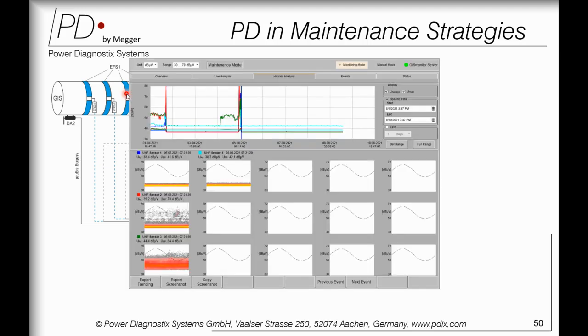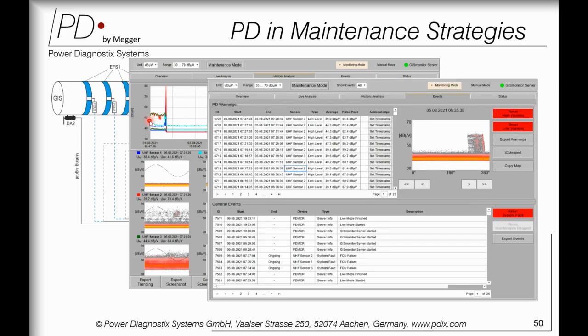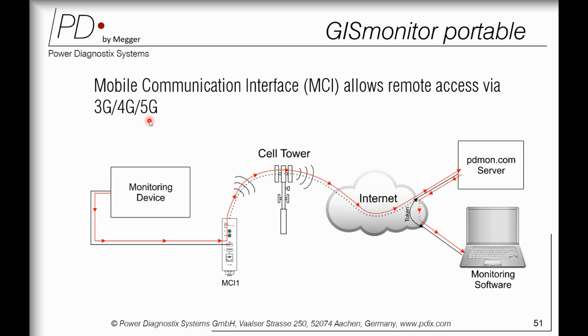The software is capable of temporary monitoring. You can connect up to 8 channels and go up to 40 channels in future, where you capture the PRPD patterns. You have a voltage where you do the trending, along with date and time and dB microvolt values. It also captures all the events, each and everything, because we are using the same software that we use for the GIS monitoring system. So it gives all the capabilities of the maintenance strategies, like trending, monitoring, spot measurement, and all.